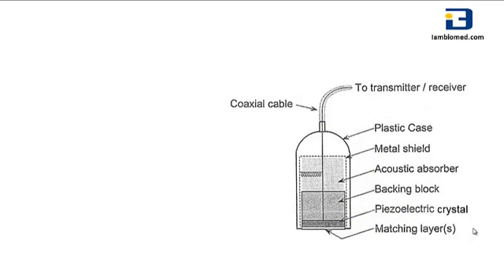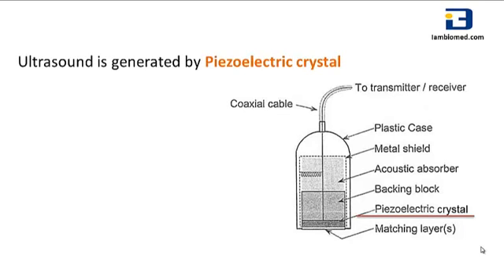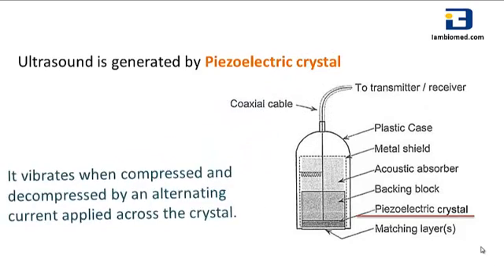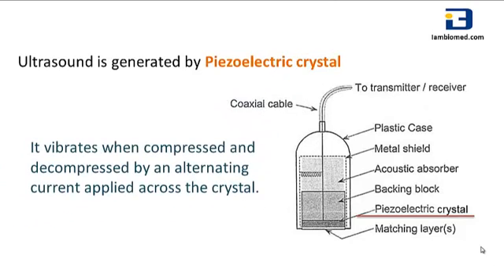The image shows the internal components of an ultrasonic transducer. The most important component is the piezoelectric crystal. Ultrasound is generated by the piezoelectric crystal, which vibrates when compressed and decompressed by an alternating current applied across the crystal.